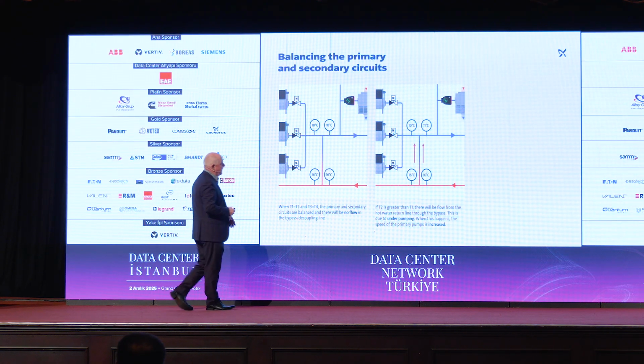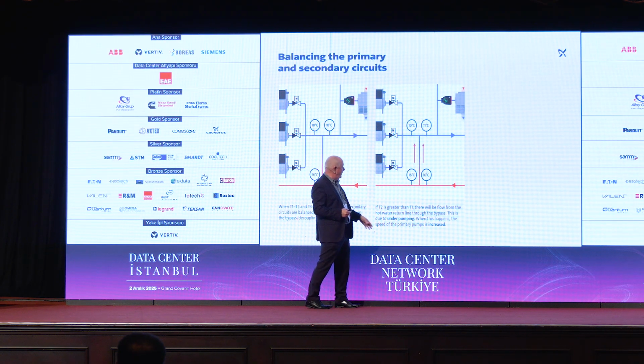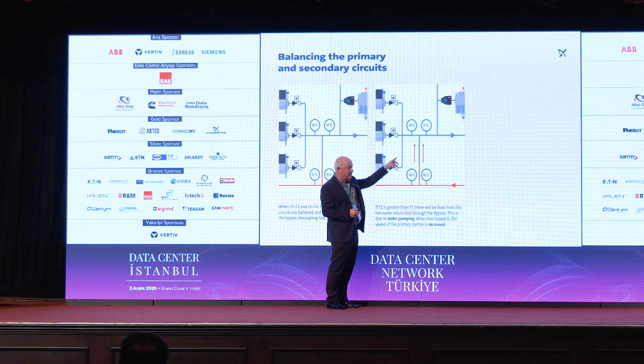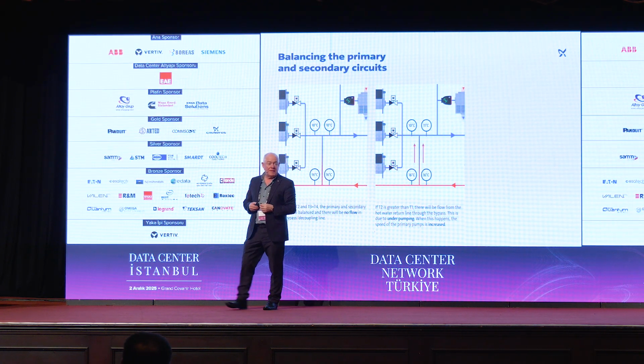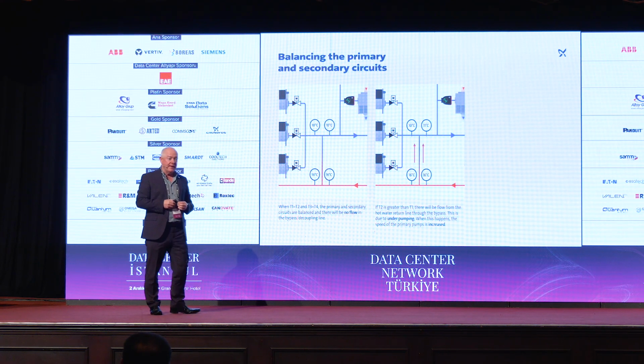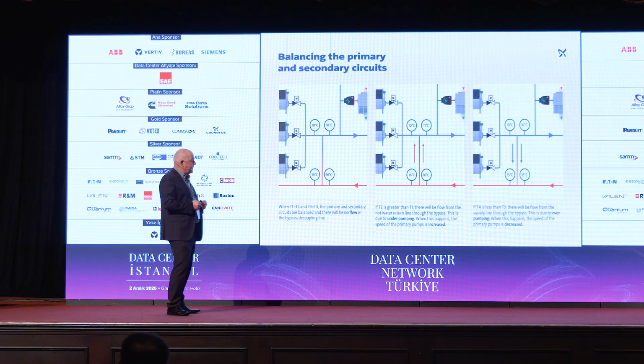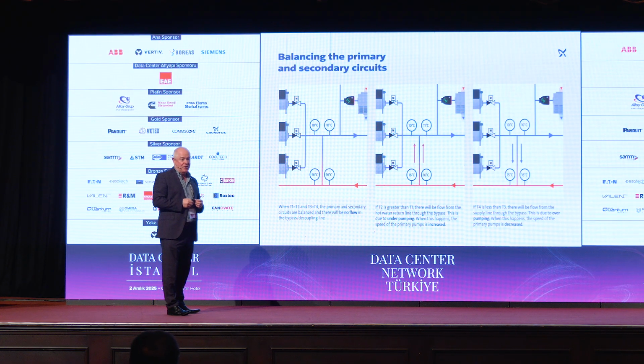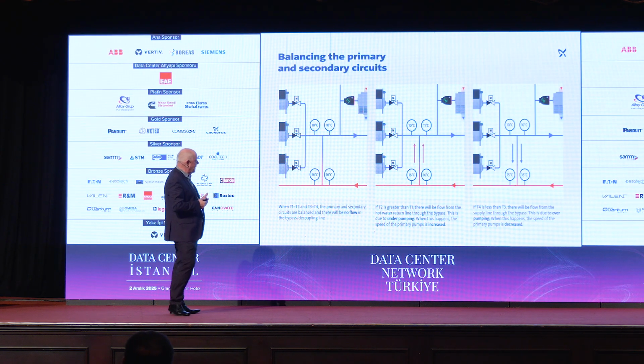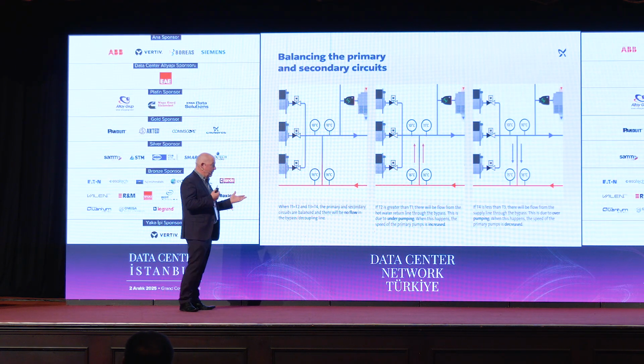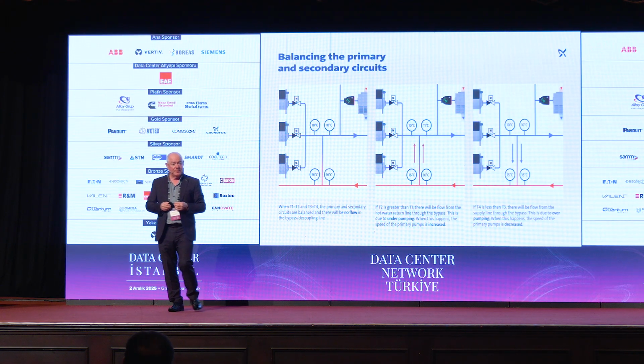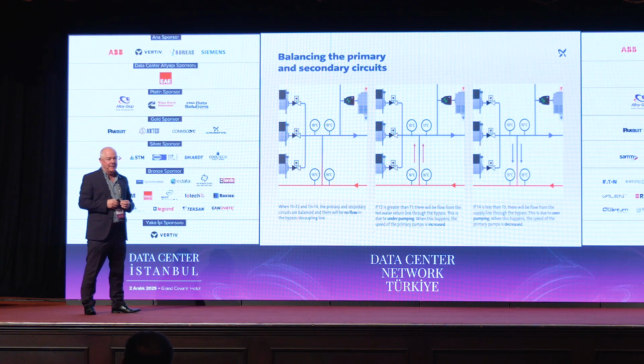Over here, it's gone out of balance. We can see we have 11 degrees up here. So we're under pumping. We're recirculating through the decoupling line. We will speed up the primary pumps to meet that demand. And the opposite's happening over here. We're over pumping, and in this situation, we slow down the pumps, and it'll happen very, very quickly, and constantly we will be doing this. So a very, very simple way of doing something that might look a little bit complicated, keeping those two systems in balance. And as I said, it works very, very quickly.